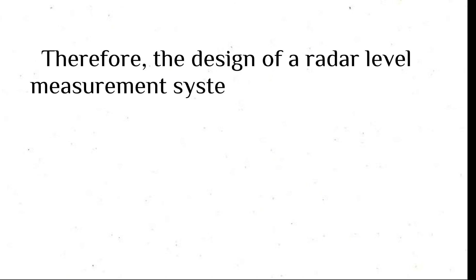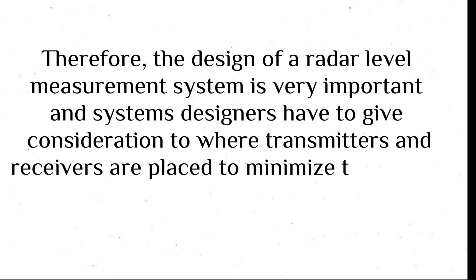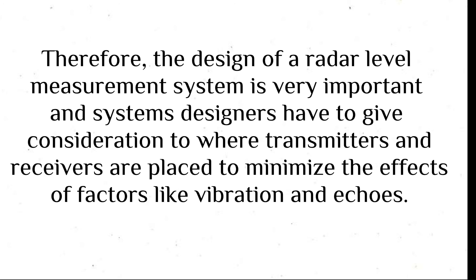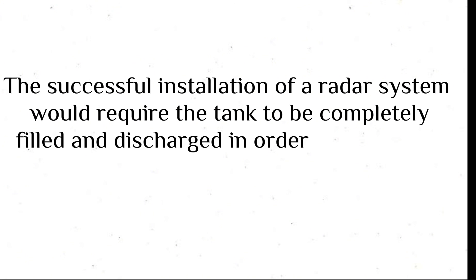Therefore, the design of a radar level measurement system is very important and systems designers have to give consideration to where transmitters and receivers are placed to minimize the effects of factors like vibration and echoes. The successful installation of a radar system would require the tank to be completely filled and discharged in order to determine level measurement accuracy.